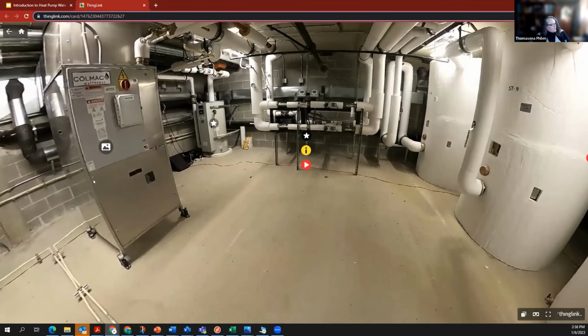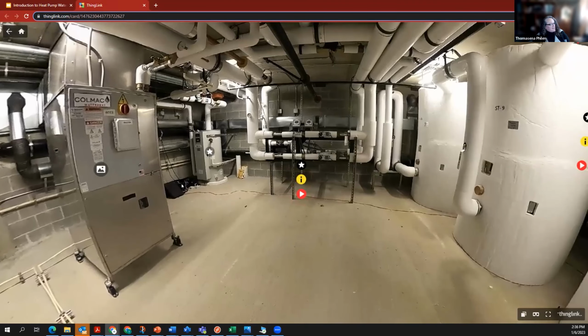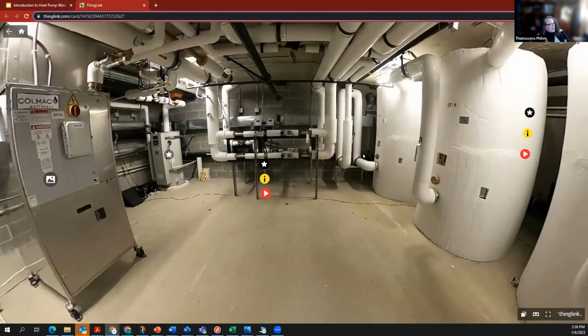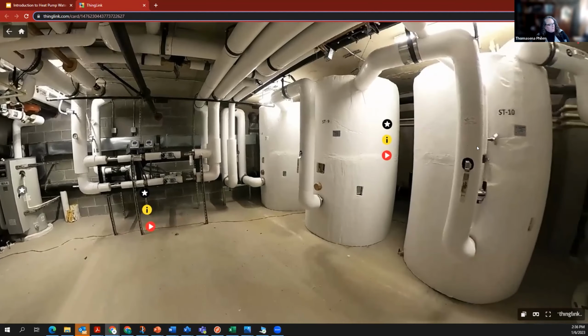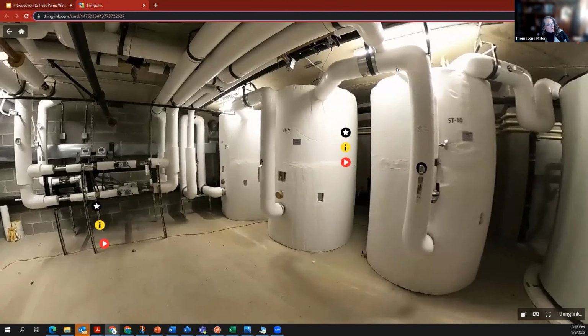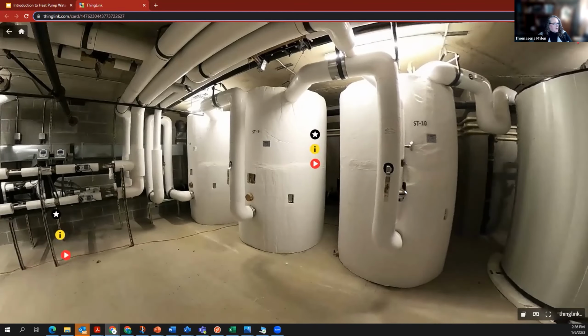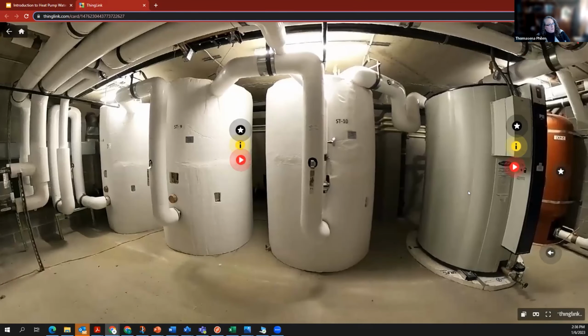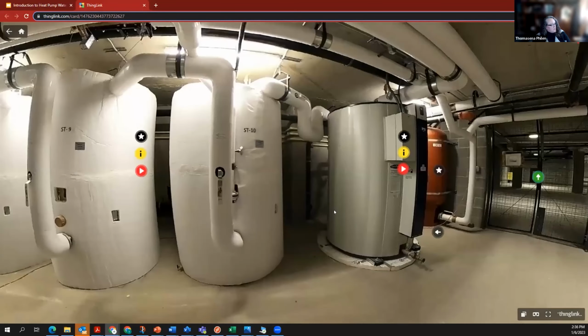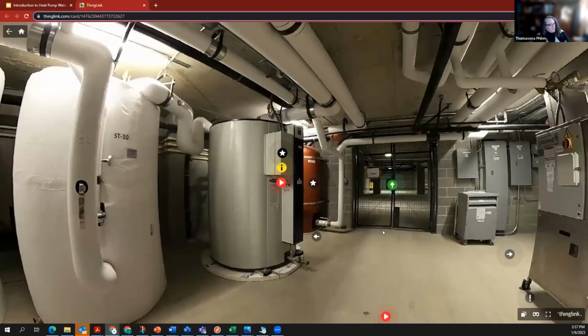The other thing is I've got a heat pump here and it has its own COP, but what really matters when you're dealing with a system like this is the system COP, because we have so many multiple components on a single system. We want to maximize and optimize every aspect of the system itself. And so there we have very heavily insulated piping throughout. These 3 tanks are in a series, they are connected. And there's a lot of information available out there about tank stratification and recirculation and how important it is to have a temperature maintenance or a swing tank involved. Even training out there about the expansion tanks that's available now. But this is the tour, and there will be a link for it in the PDF that I'll be making available to Larry after this presentation.